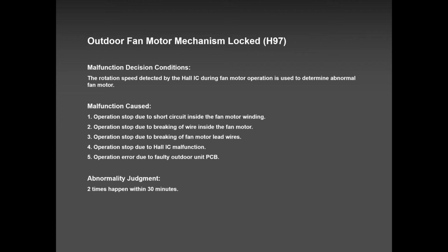So the moment I get a call, Paul, with this error code H97, I haven't been to the outdoor unit. I tell them, go and check the outdoor unit. One job site was so funny; he told me, Paul, I can't see where the outdoor unit is. And I told him, I have not installed this unit. Who installed it? He said, I don't know who installed it. Guess what? It was covered with snow. A lot of snow. They had a snowstorm. So guys, sometimes the unit gets covered with snow, which is very rare, but it can happen. But most of the time, snow goes into the unit and holds the fan blade during a snowstorm.